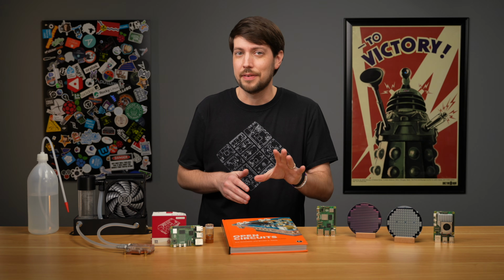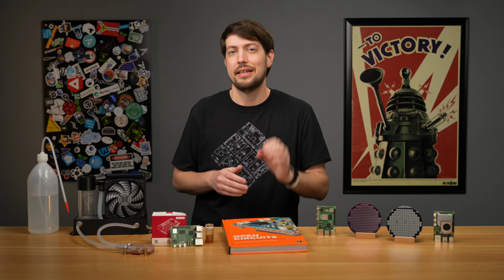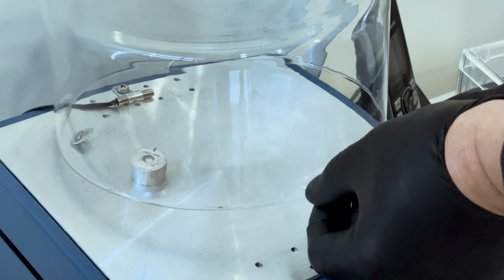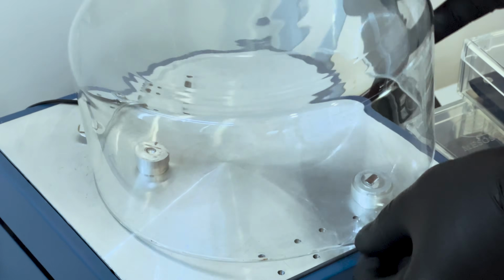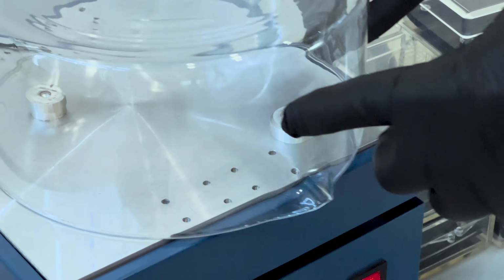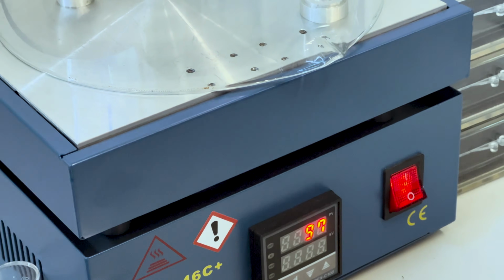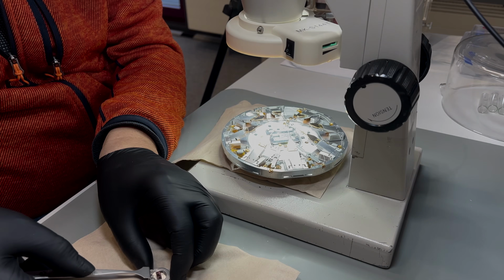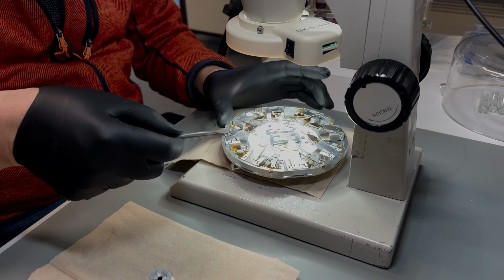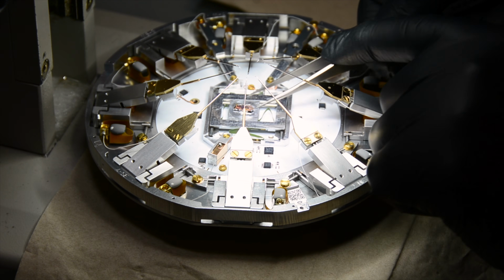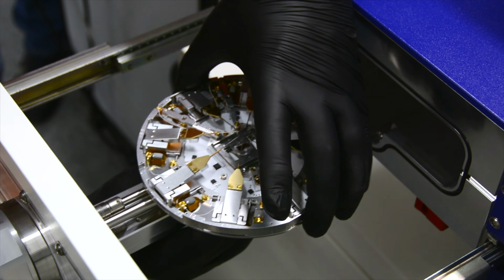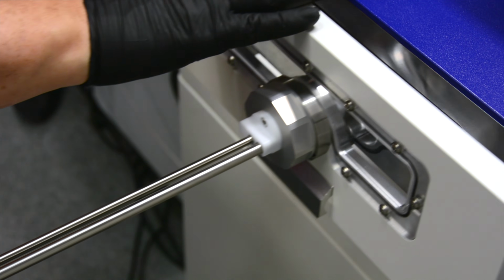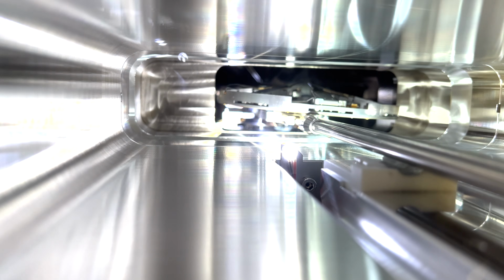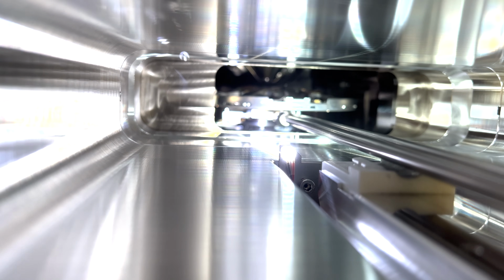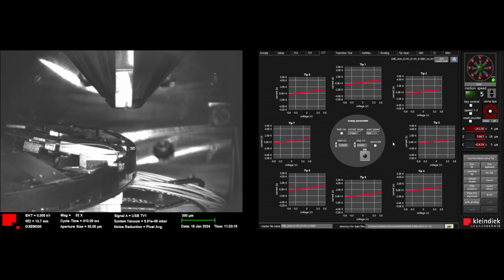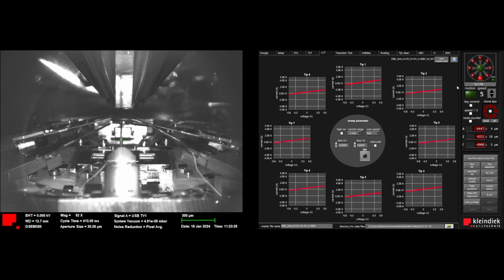But that's not enough. They also need to get rid of any organic compounds. To do that, they bake it on a hot plate at about 90 degrees Celsius for a while, covered with glass. They also use gloves and special tools when they touch the chip. The point is, even before they put the sample in the chamber, they want it as clean as possible. They place it on the prober shuttle with all the probes and load the whole thing into the SEM's vacuum chamber. First, they load it in through a smaller load lock chamber. Then, once it's inside the microscope's vacuum chamber, they run a plasma over everything to burn off any remaining contaminants. And finally, after clearing the gas they just created, they can fire up the electron beam.